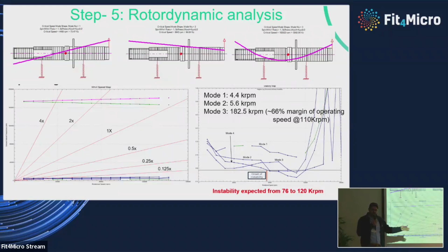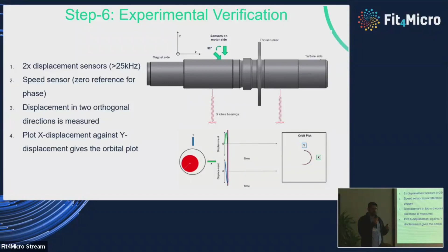Any shaft that is rotating will generate a sinusoidal signal if you put two displacement sensors. Here you have a displacement sensor to measure the vibration in Y. Here you have the vibration measurement in X. And when you plot them, you get something called a shaft orbit. You need to know the orbit because this defines whether you are going to touch your bearings or not.